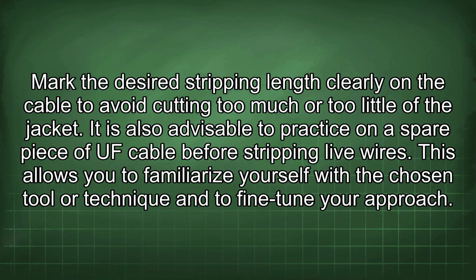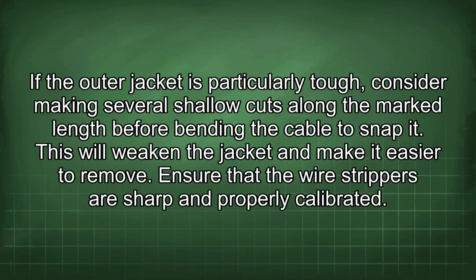It is also advisable to practice on a spare piece of UF cable before stripping live wires. This allows you to familiarize yourself with the chosen tool or technique and to fine-tune your approach. If the outer jacket is particularly tough, consider making several shallow cuts along the marked length before bending the cable to snap it. This will weaken the jacket and make it easier to remove.